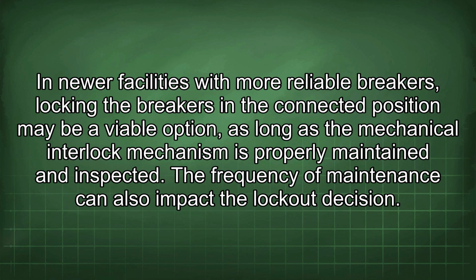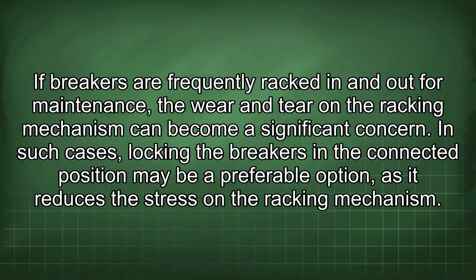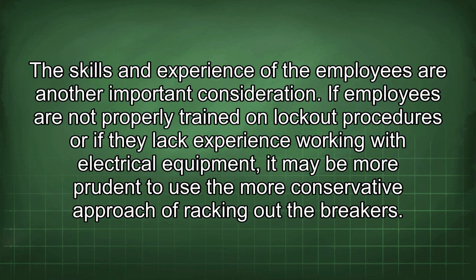The frequency of maintenance can also impact the lockout decision. If breakers are frequently racked in and out for maintenance, the wear and tear on the racking mechanism can become a significant concern. In such cases, locking the breakers in the connected position may be a preferable option as it reduces the stress on the racking mechanism. The skills and experience of the employees are another important consideration. If employees are not properly trained on lockout procedures or if they lack experience working with electrical equipment, it may be more prudent to use the more conservative approach of racking out the breakers.